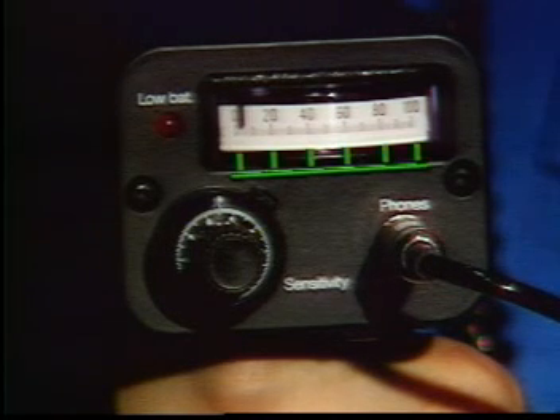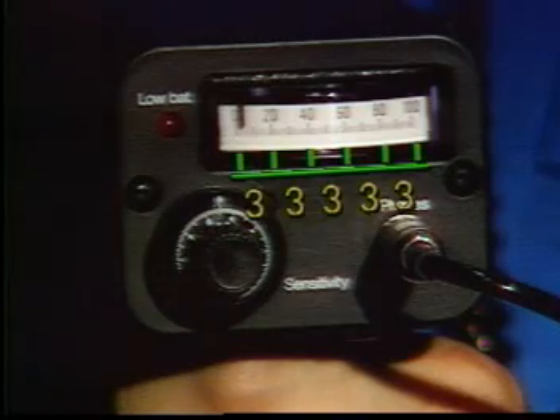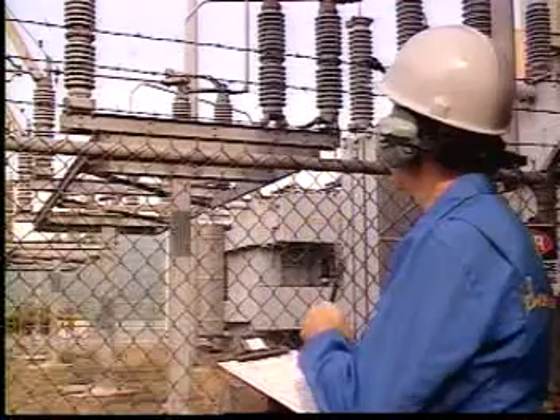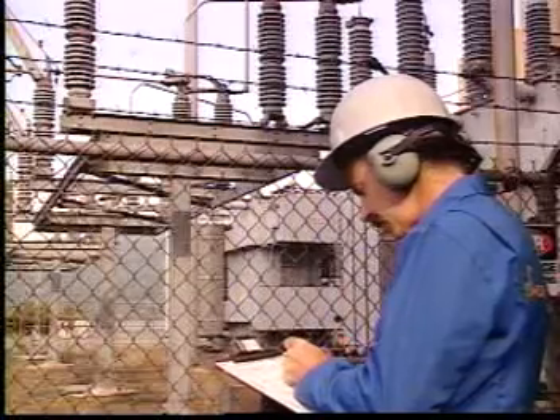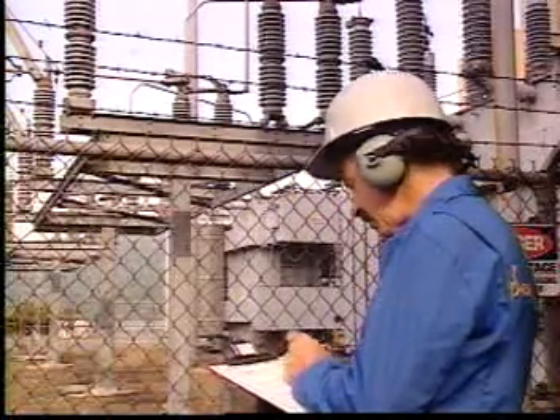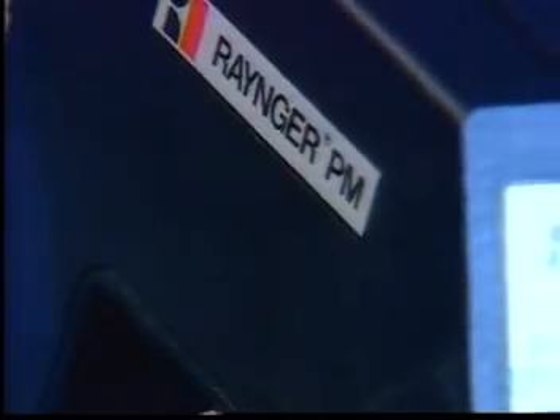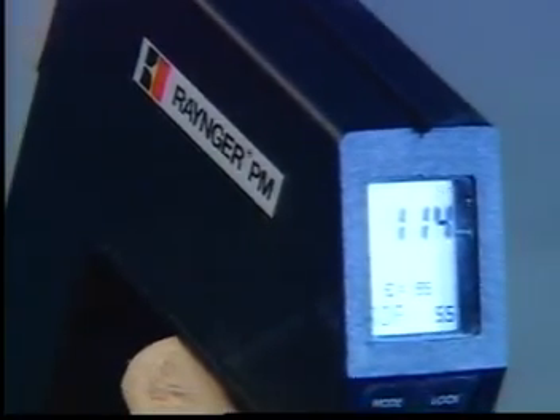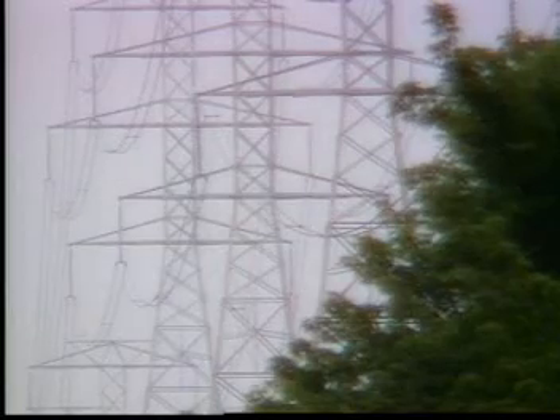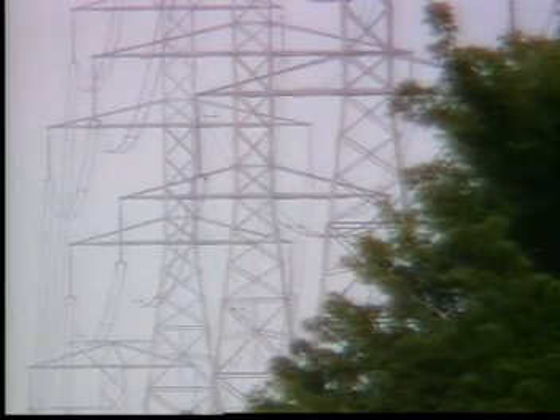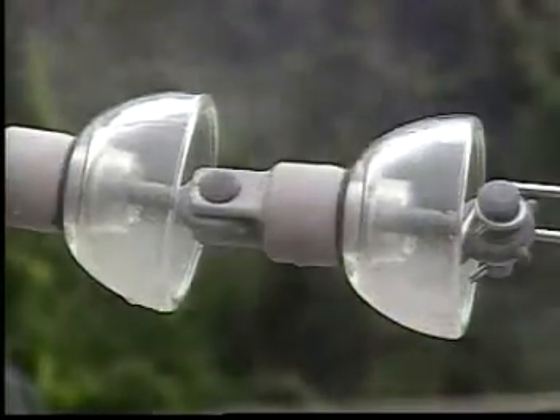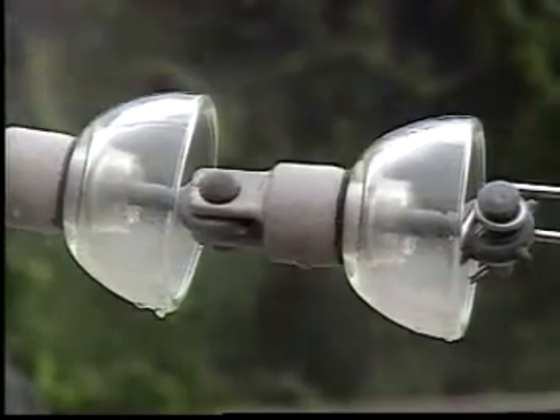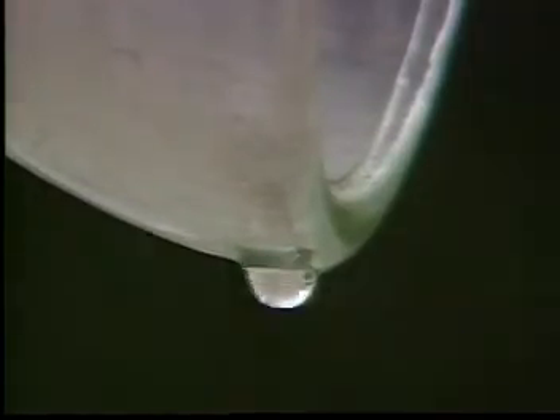In the LIN scale, every change of 20 increments on the meter is approximately 3 decibels. Note whether you heard arcing, tracking, or corona, and include the location. Also make note of the temperature and relative humidity at the time of testing. You'll find weather conditions affect the results and should be taken into consideration when making comparisons. As an example, high humidity or rain will allow for greater arcing, tracking, or corona.